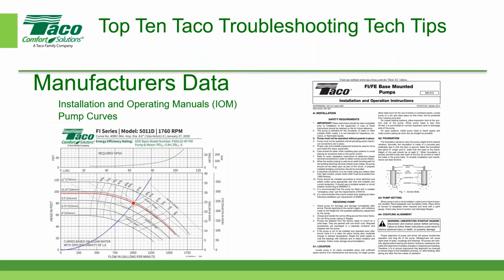So actually this came up not too long ago, a couple of weeks ago. Someone said that they were having some issues with an FI base mounted pump, and when they sent me the photograph, it revealed that it was a vertical inline, and the model number that they originally gave me was incorrect. But they did have a photograph of the pump tag, and so we were able to get our manufacturer's data in this case. So what kind of data does the manufacturer have available?